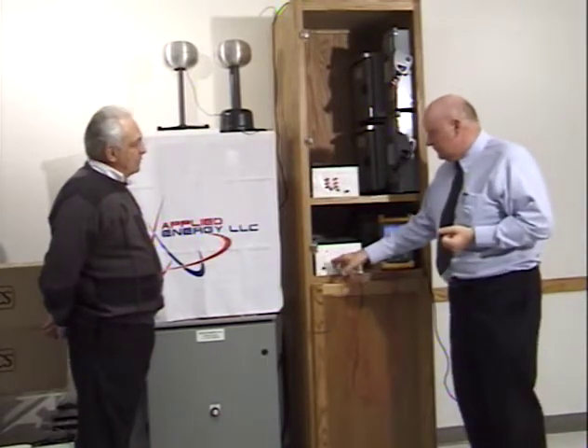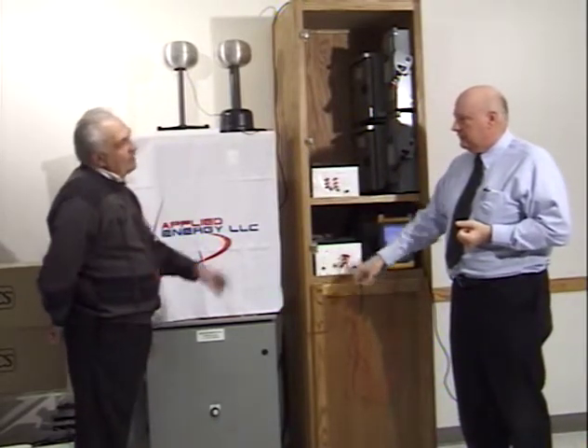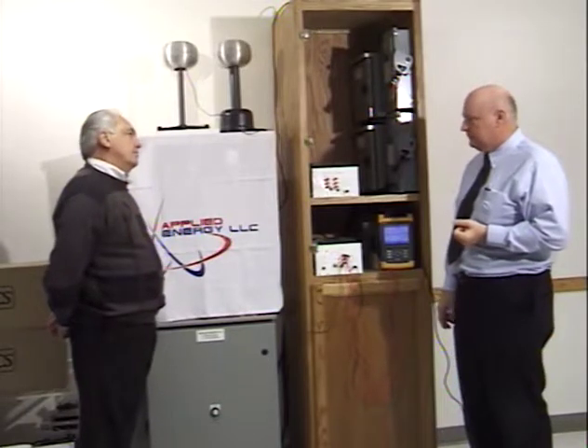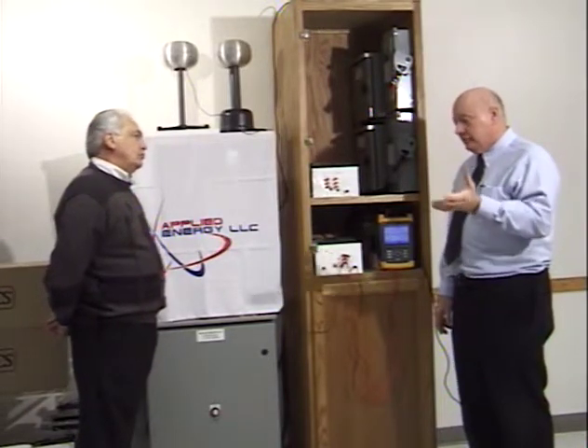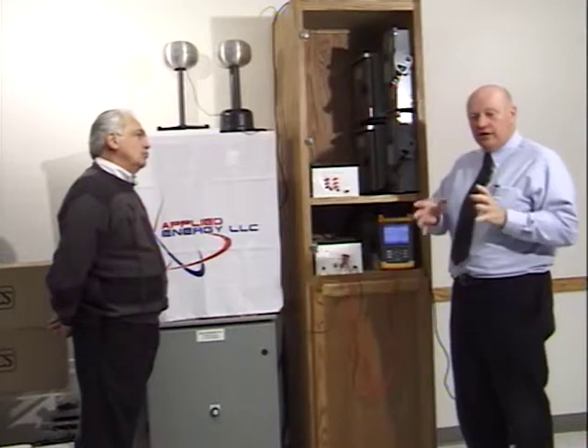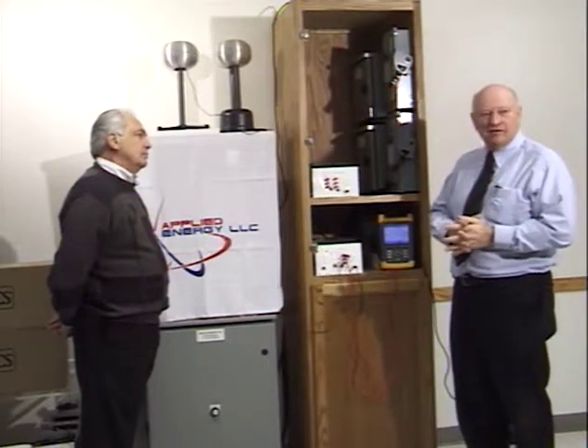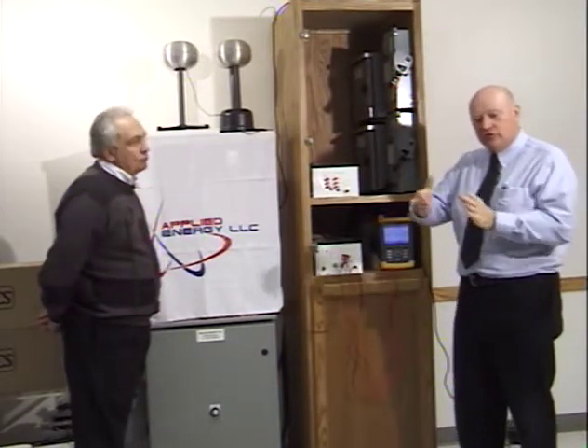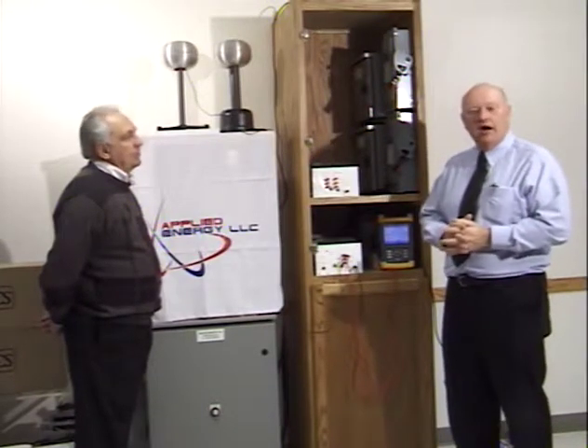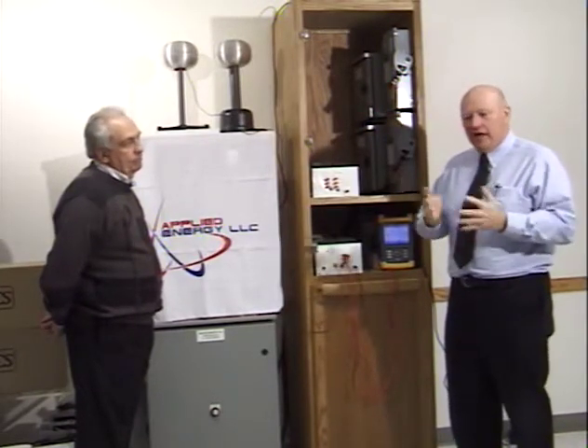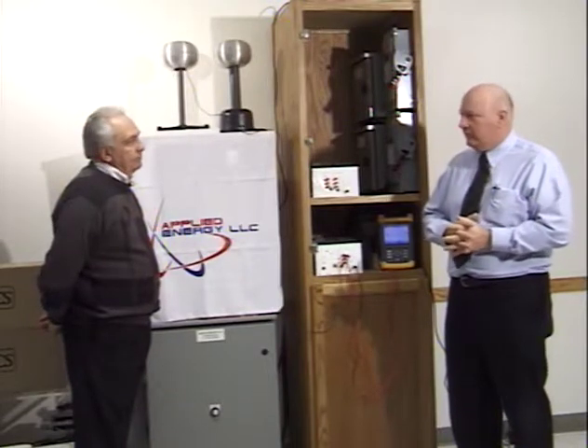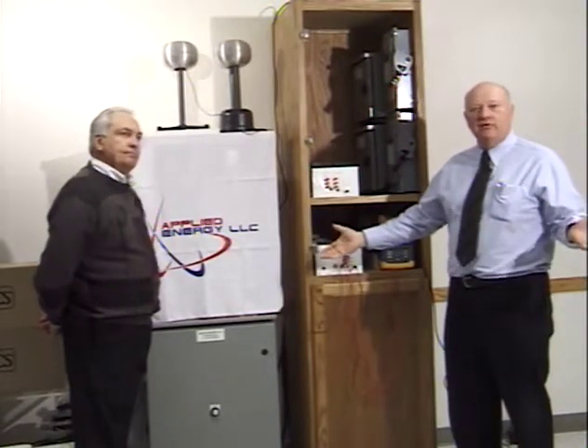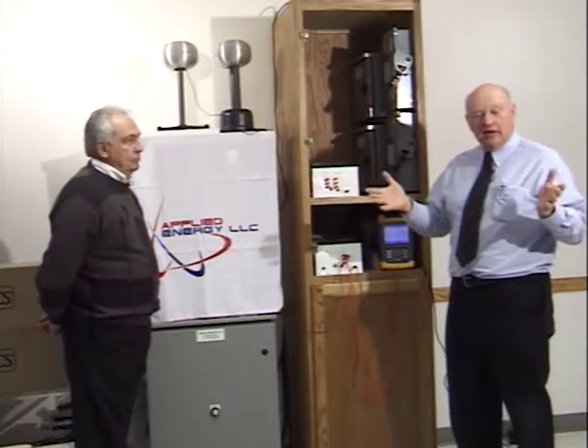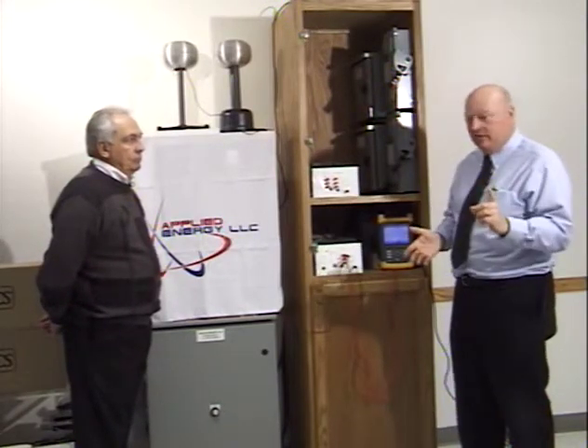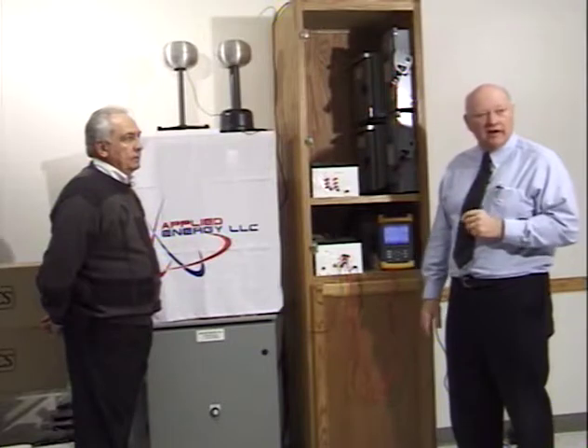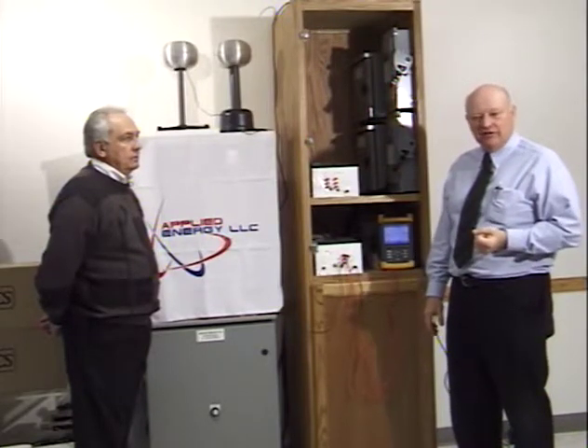So Bill, then what we're actually looking at here is we've got one product with three distinct benefits. Exactly. Surge suppressor companies tell you you need a surge suppressor for every sensitive load, and you need to put them as close to the source of the noise as possible. That's to minimize clamping voltage, right? Yeah, and how do you know where the source of the noise is going to come from? With Phaseback, it doesn't make any difference where it comes from. A facility that has one power transformer needs one Phaseback, and every piece of equipment in that facility is protected.